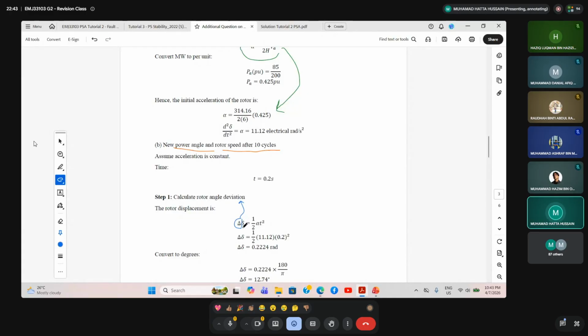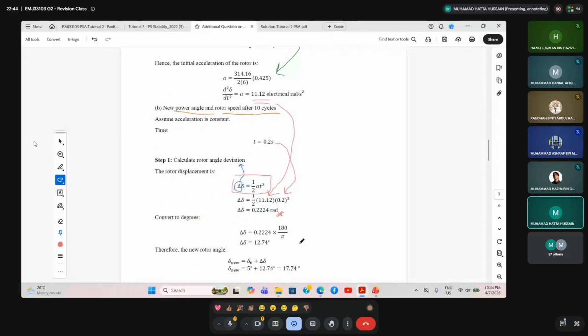The delta here is actually the rotor angle deviation. By using this standard formula here, rotor angle deviation equal to half times the acceleration times t square. Because I know from part A here, 11.12, and then t is equal to 0.2 second. So I have the rotor angle deviation is 0.2224 radian. And of course, I need to find also in degree, right? In degree. So by using the standard formula here, times 180 degree divided by pi, I have 12.74 degree.